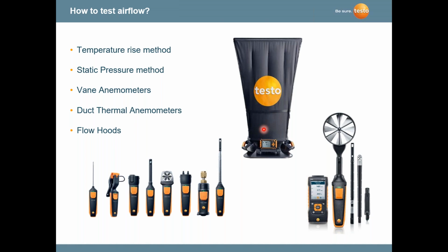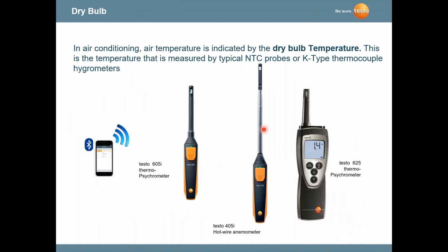Not only is airflow measured to improve equipment performance, but over the last 2 years, airflow is being measured quite more frequently because of indoor air quality issues, primarily because of the COVID-19 issue we have had over the last few years. By improving the airflow, we can improve the indoor air quality, and that has taken a big step forward, measuring airflow in commercial buildings as well as residential homes. So enough with the airflow side. Let's get back to the AC side.